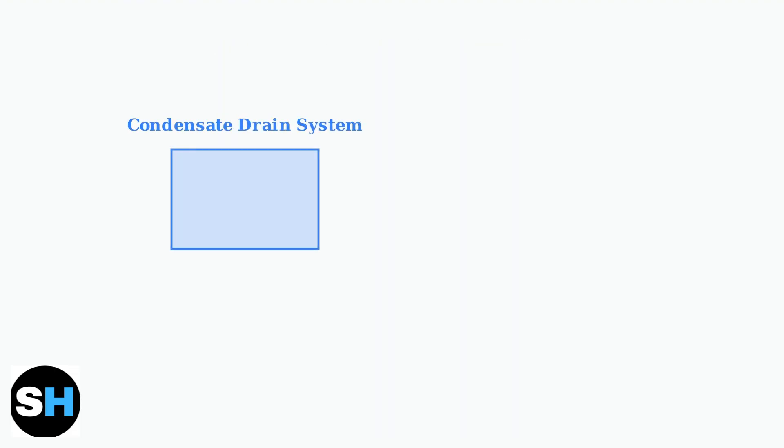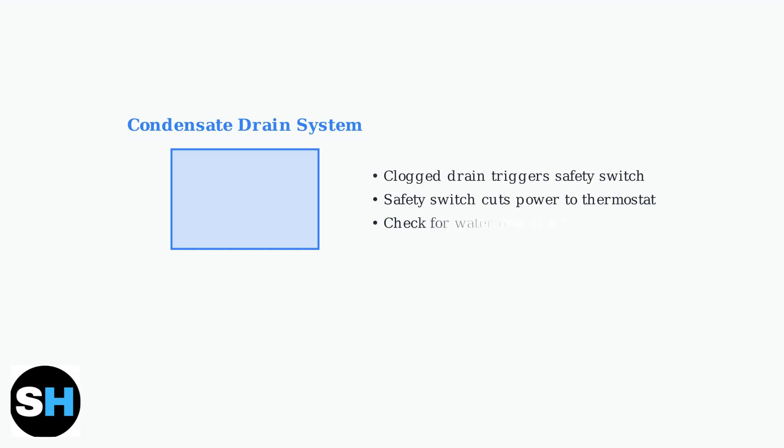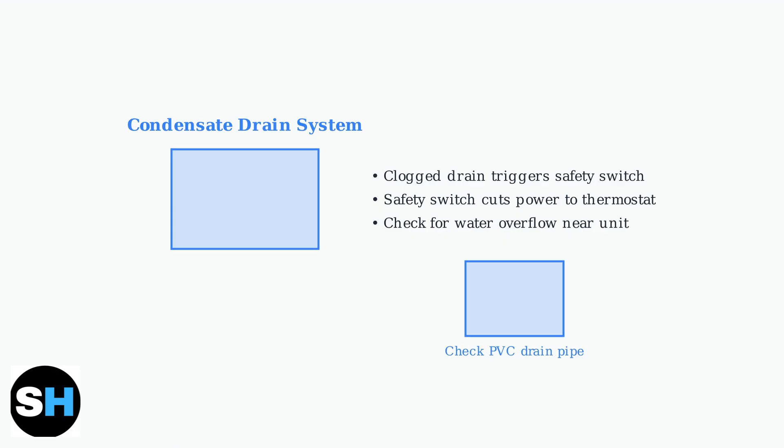First, check for a clogged condensate drain line. This is one of the most common causes of thermostat black screens that people overlook. A clogged condensate drain triggers a safety switch that shuts down your AC system. This cuts power to the thermostat, causing the black screen. Look for water overflow or standing water near your HVAC unit.